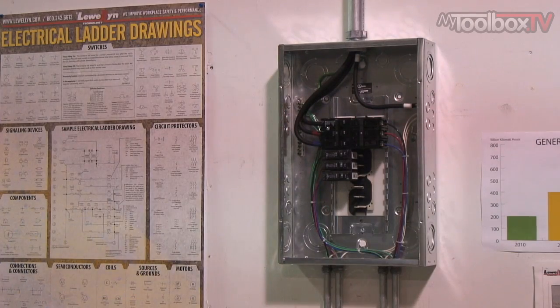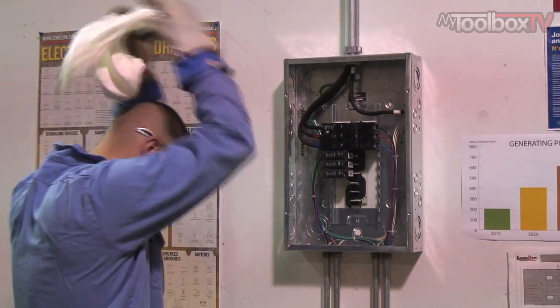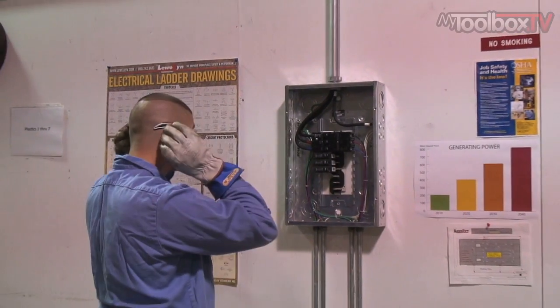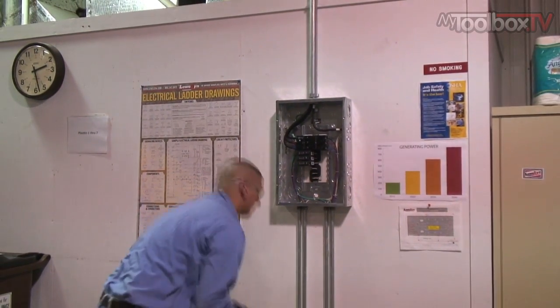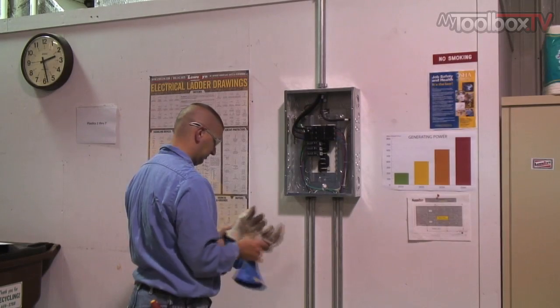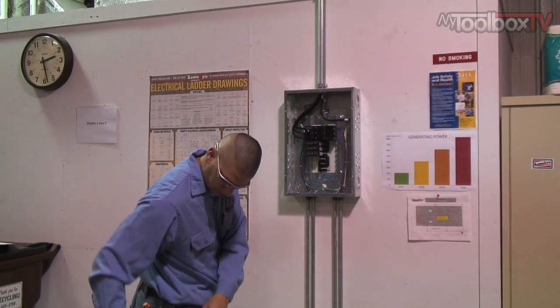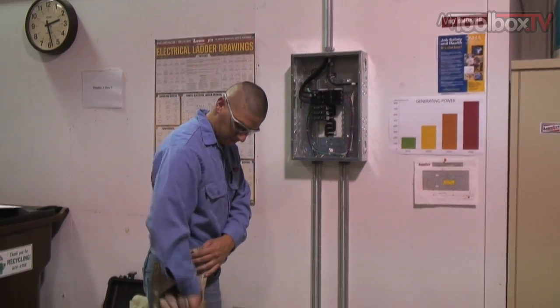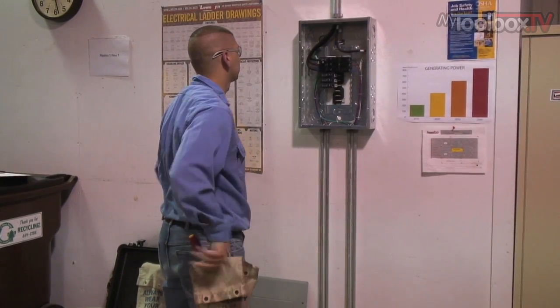If you have to be away from the panel while the panel is open, you can't just leave it open like that. Maybe you walked away to test your meter. You can't just leave the panel open. What we've done here is using an attendant. Daniel's been asked to come and watch the panel to keep people away from the panel while it's hot. Daniel is also a qualified person.